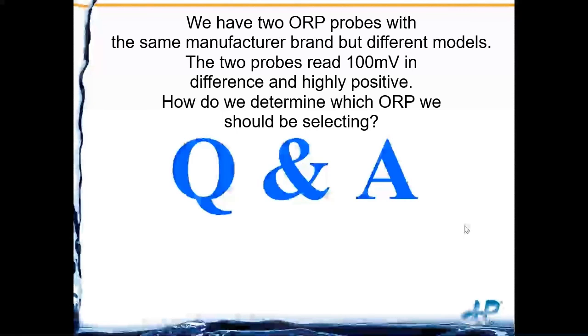Question: we have two ORP probes from the same manufacturer but different models — they read 100 millivolts apart in a highly positive application. How do we determine which is correct? Start by isolating them. If you have quick-disconnect cables, swap the probes and see if the 100 millivolt difference follows the sensor or stays with the transmitter. If it follows the sensor, investigate that sensor; if it stays with the transmitter, look at the transmitter age and cable.